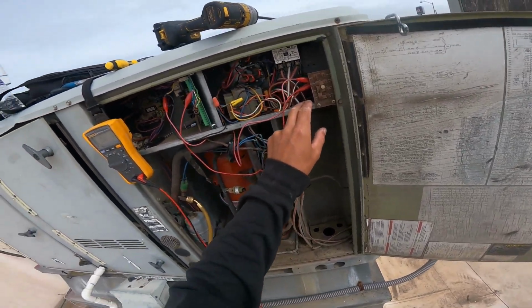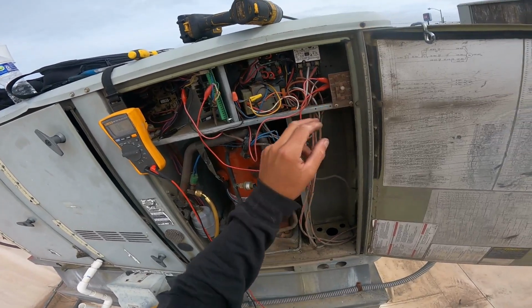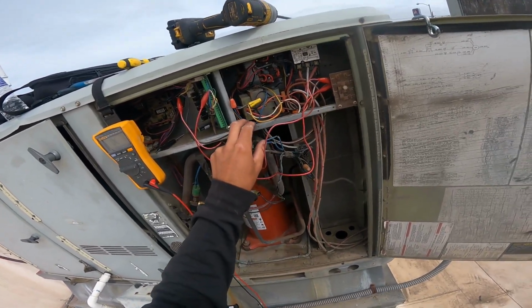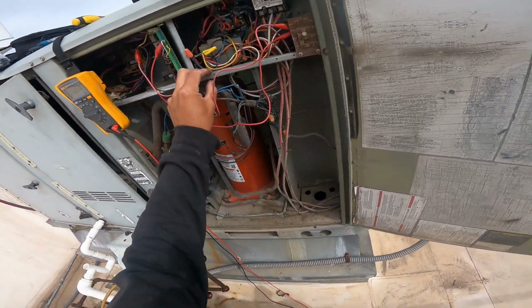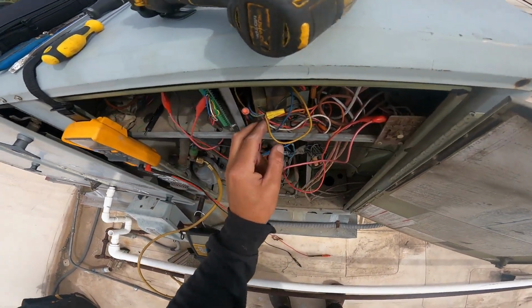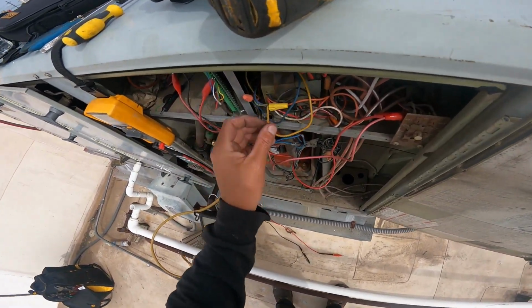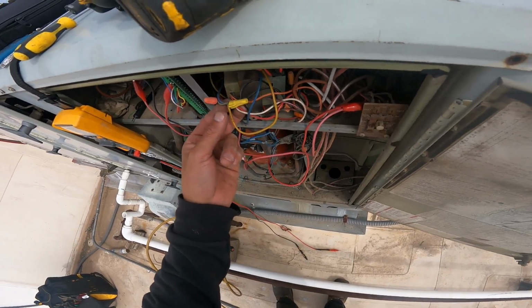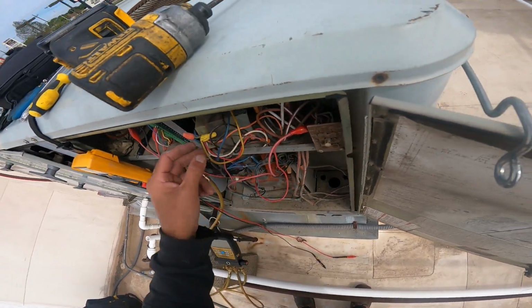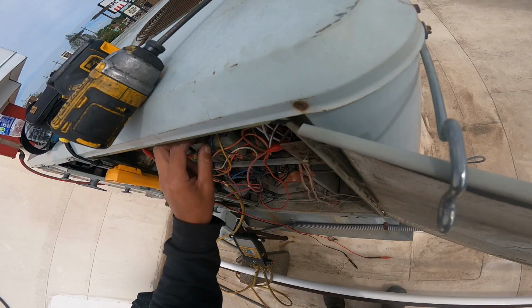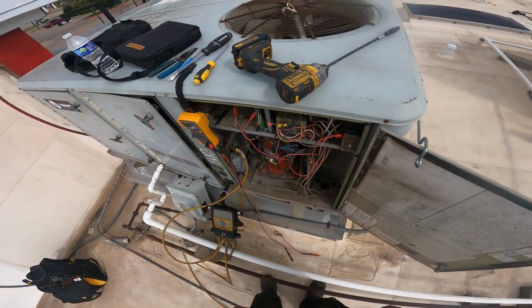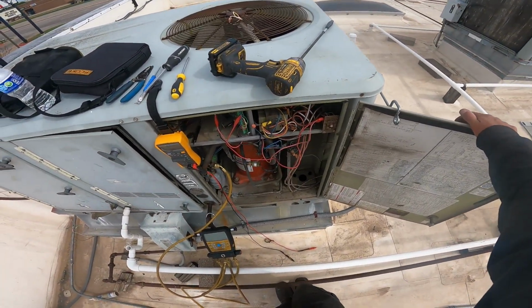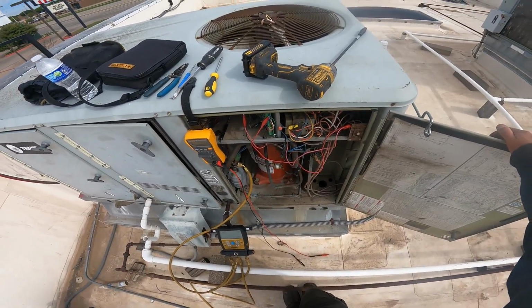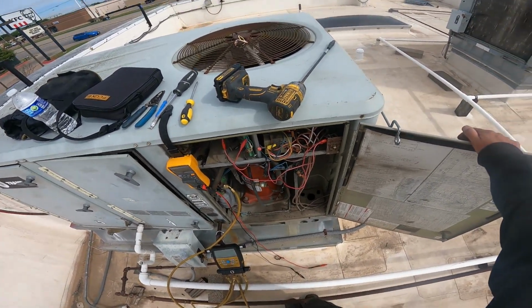This is 24 VAC, that's all I'm supposed to be feeding. Somehow this transformer is giving a whole lot more than that. So this is not the original transformer, and you can wire them up for different voltages, and I kind of wonder how they wired this one up. Transformer was tripped. There are so many problems in this. If the transformer's tripped, I shouldn't be getting any voltage to anything low voltage.